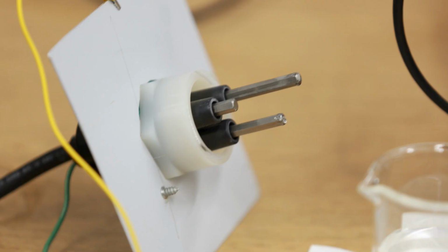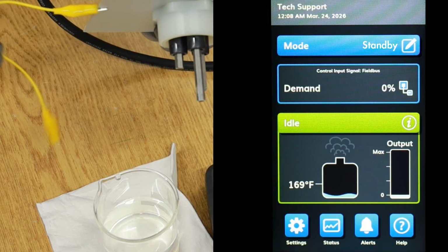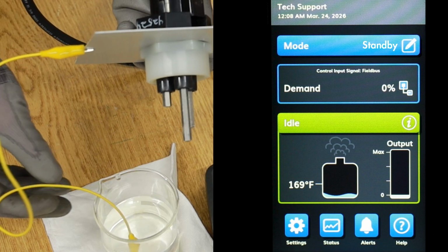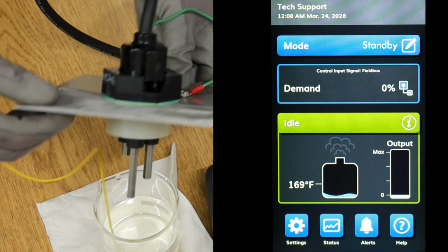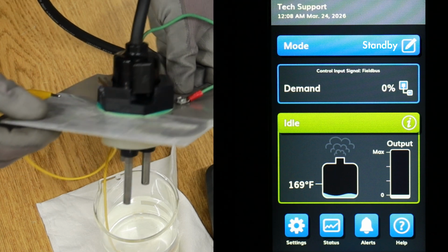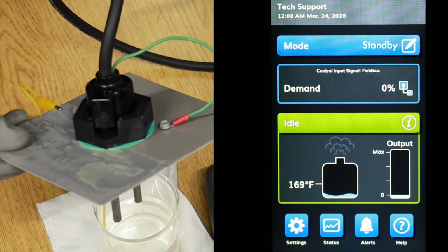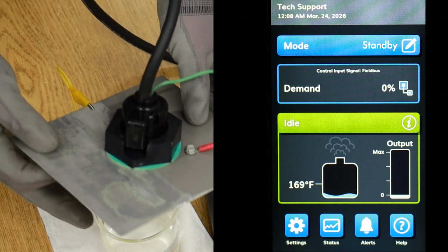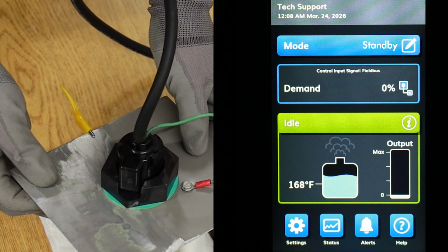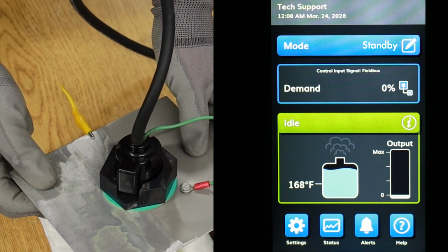Here's a probe assembly with the cup removed. For this demonstration, the yellow wire establishes a path to ground on the tank. We will look first at the water level indicator when the probes are properly wired. Watch the indicator on the screen as the probes contact water. Shown now is no water. Water touches the low probe, then the middle probe, so the tank is full.